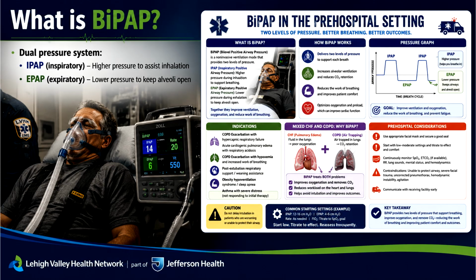Those two pressures are called IPAP and EPAP. Let's start with IPAP, or inspiratory positive airway pressure. This is the higher pressure that's delivered as the patient inhales. Its primary job is to assist the patient's inspiratory effort. Think of IPAP as a gentle push with every breath.